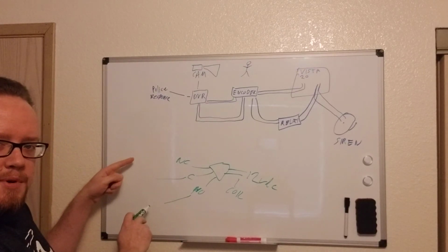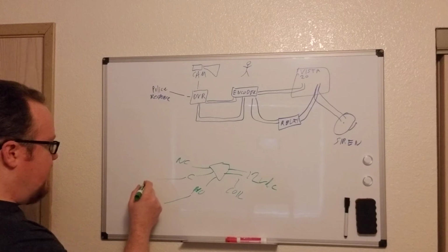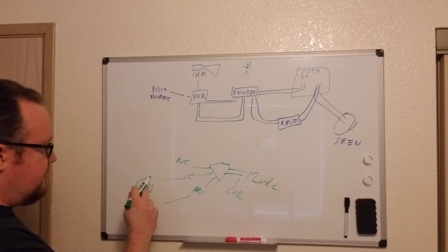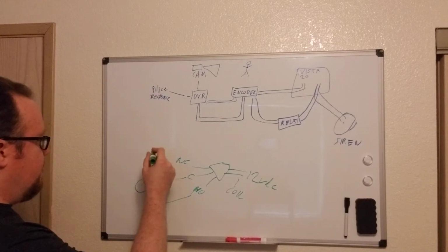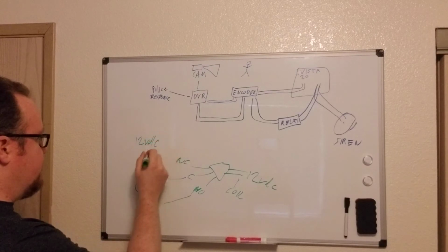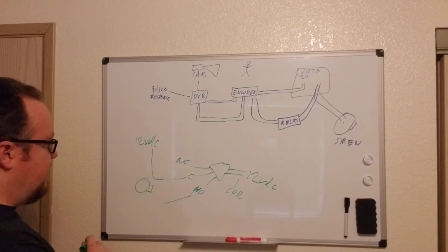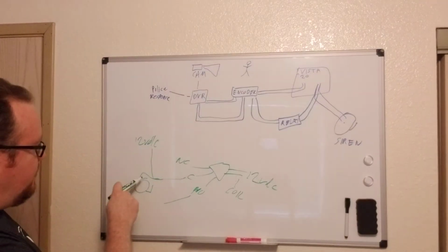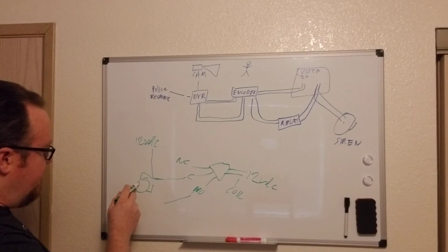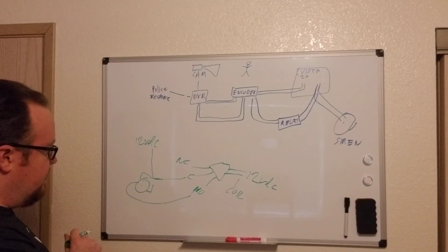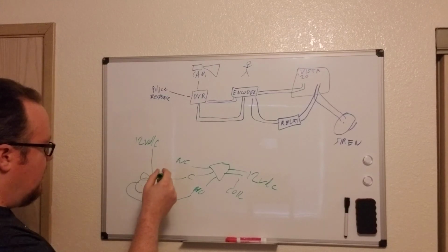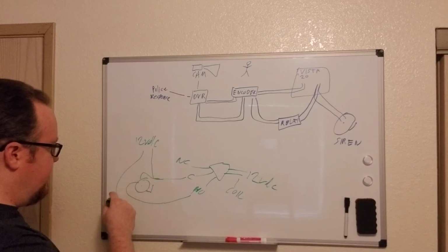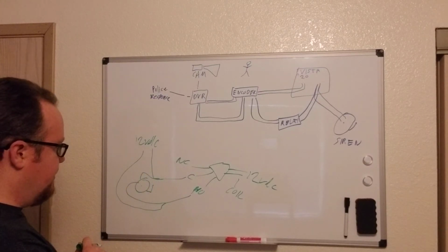These are kept apart. So let's say you've got a siren. I'm just going to use a bell here. And so the siren goes off when 12 volts is applied. So you have a 12 volt DC power source. One leg of that goes in on the common, and it's also paralleled with the leg off the bell here. And then the bell just goes straight to the normally open, like so. And then the other side of the 12 volt DC also goes here.